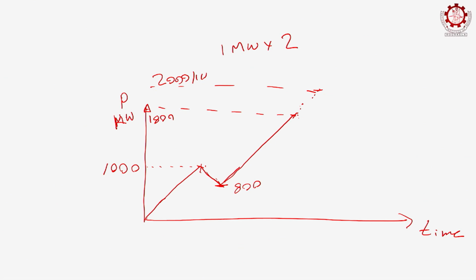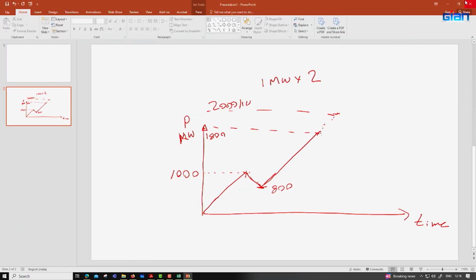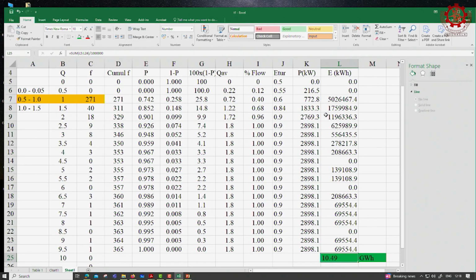So, all these things will enhance the total power generation. Accordingly, you have to think about this when you have multiple turbines, how your plant generates electricity. Therefore, you can further increase the total by optimally operating the two turbines and accordingly reflecting that in this Excel sheet, rather than saying one turbine until it is fully loaded we take it, and then the rest of the water from the beginning we load onto the other one.